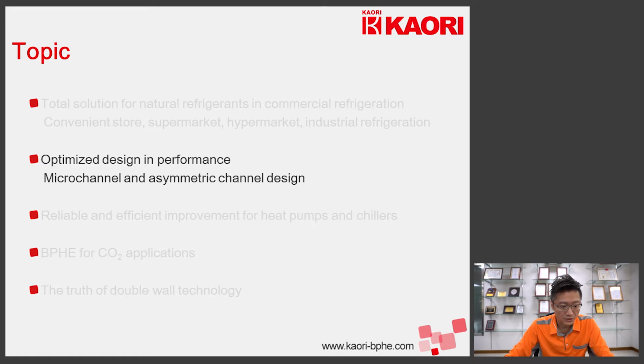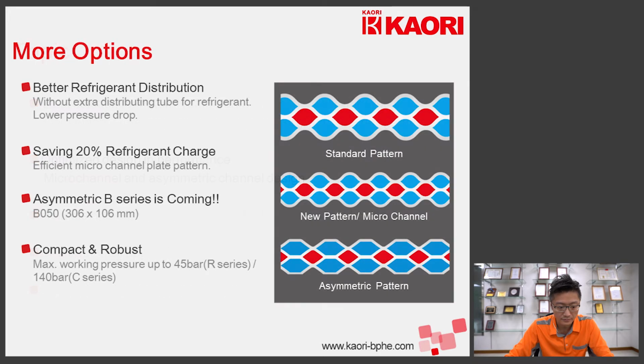In this topic, let's look at how microchannel and asymmetric design can improve the performance. In Kaori, we offer customers more options. If we look on the right side of the slide, it shows a few different cross-sections of the brazed plate heat exchangers. The first pattern is the standard or conventional pattern. As you can see, both sides have the same volume. And the second pattern shows the microchannel. Both sides are significantly smaller than the standard pattern. So this saves the refrigerant charge by 20%.